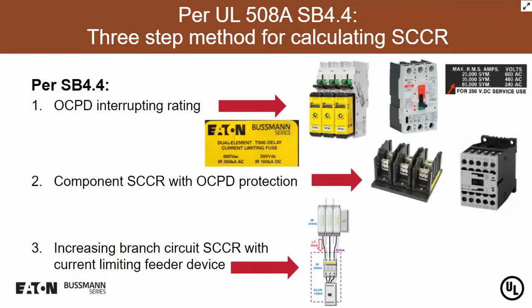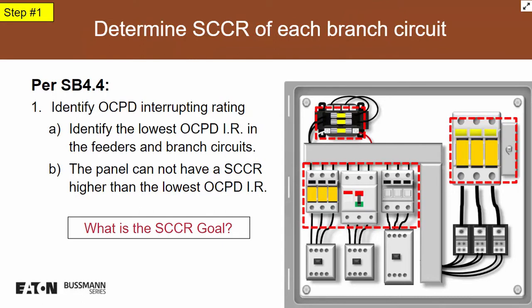And so I'm going to break this down a little bit for you. This way we can understand the different steps that we have. So let's just look at step number one. And as you can see, in the upper left-hand corner, I'm putting the step that I'm at at that time. Step number one is pretty simple. We're going to look at all of our fuses and all of our breakers in this panel, and whatever the lowest interrupting rating is, our panel can't be higher than that, and that will be our answer for step number one. So if the breakers are rated for 65,000 amps and the fuses are rated for 200,000 amps, step number one would be a 65,000 amp panel at this time.